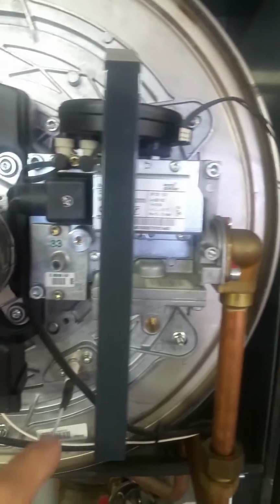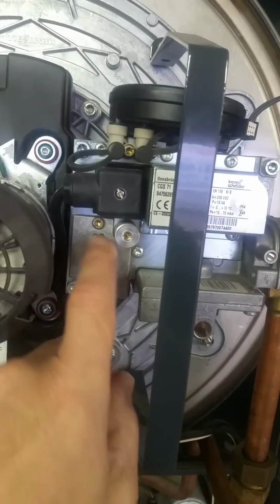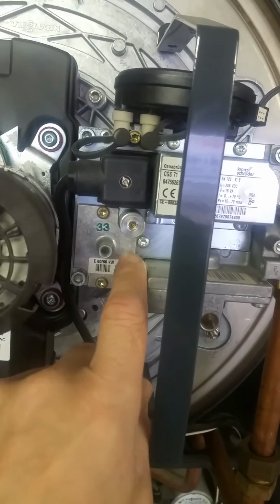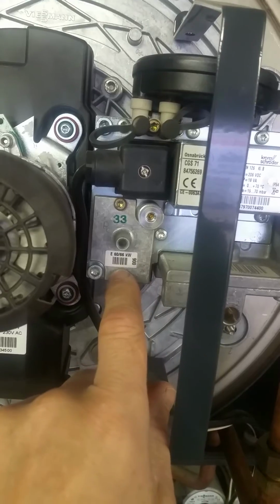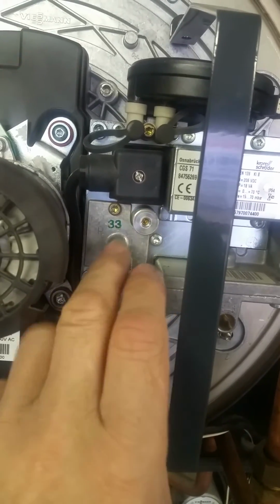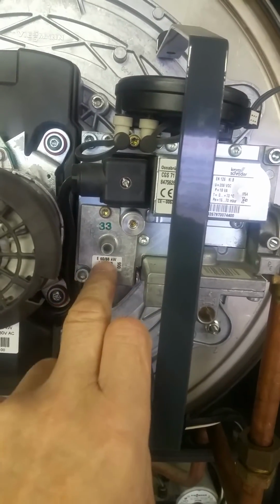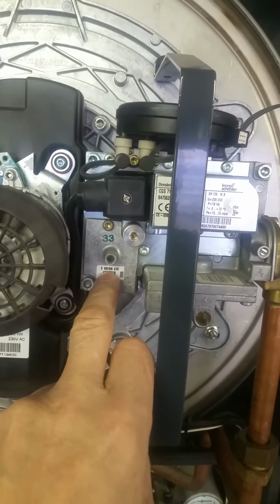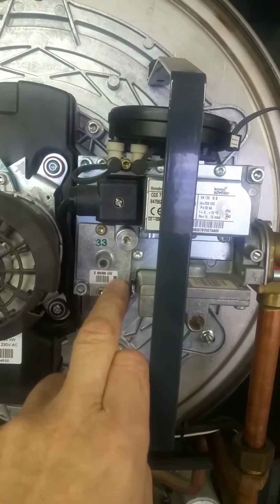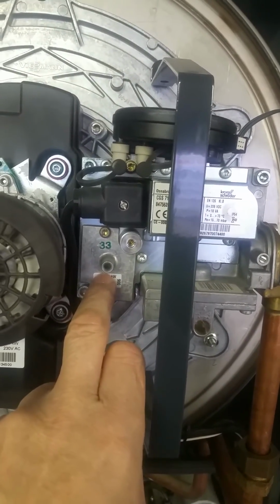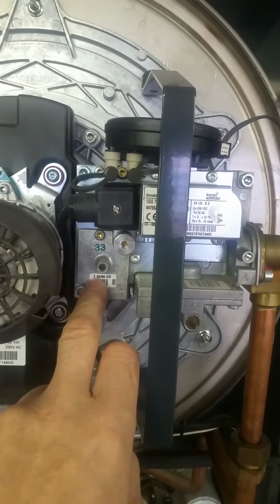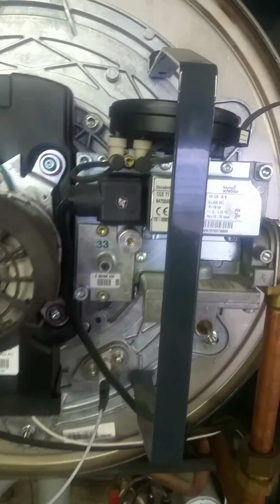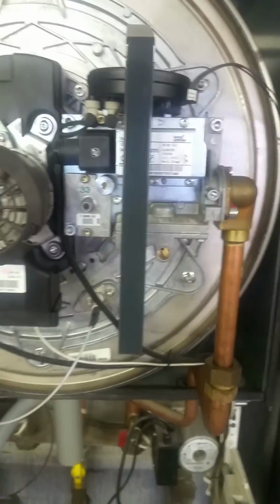And the other thing to know about these, if you ever go out to a 300, this plate needs to be changed. The gas valve arrives looking the same, but it's got a dummy plate here, and this plate has got a disc in the back which controls the rate of gas flow through the gas valve, and you must remove this part from the old gas valve and fit it to the new one, otherwise you'll get all sorts of weird combustion problems going on. So hope that helps.